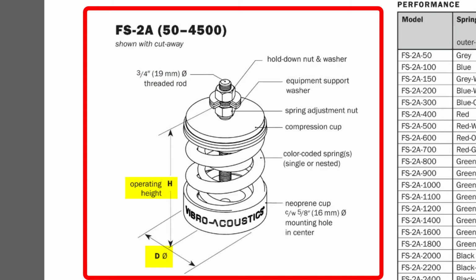The overall diameter and the operating height, which is measured from the floor to the equipment support washer, are labeled here. The diameter can be checked on the job site to confirm that the isolator is a 2-inch deflection spring, since other deflection springs have different diameters. The operating height can also be checked at the job site pretty easily.